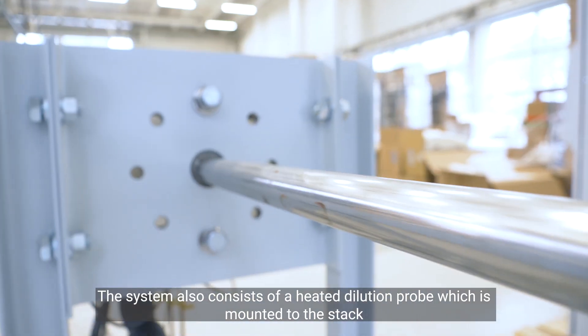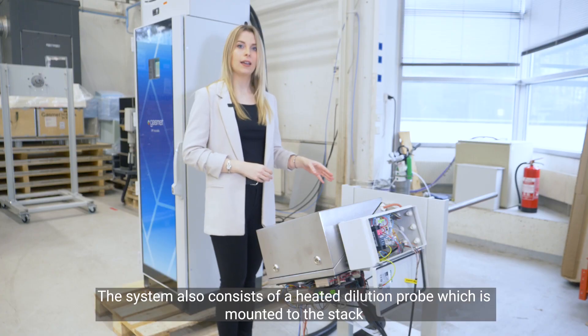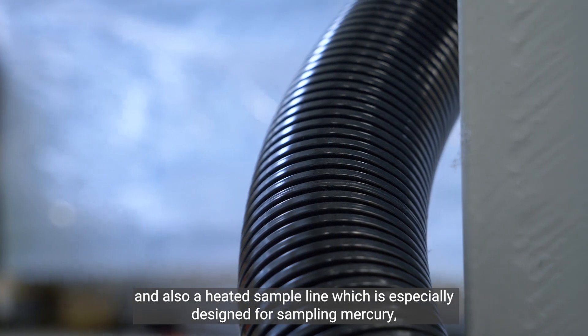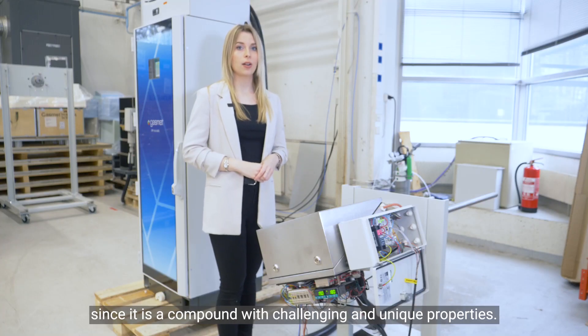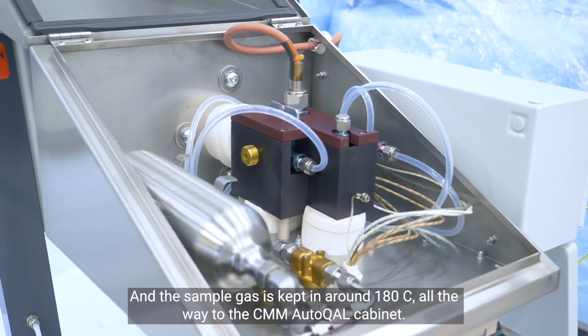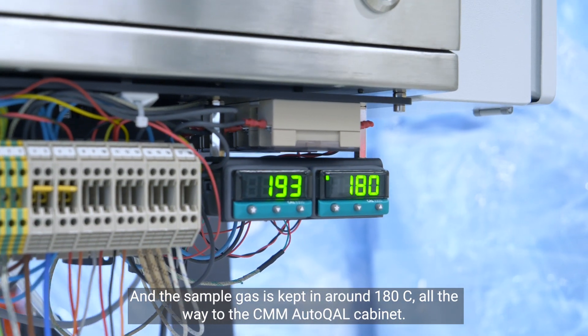The system also consists of a heated dilution probe which is mounted to the stack, and a heated sample line which is especially designed for sampling mercury, since mercury is a compound with challenging and unique properties. The sample gas is kept at around 180 degrees Celsius all the way to the CMM AutoQAL cabinet.